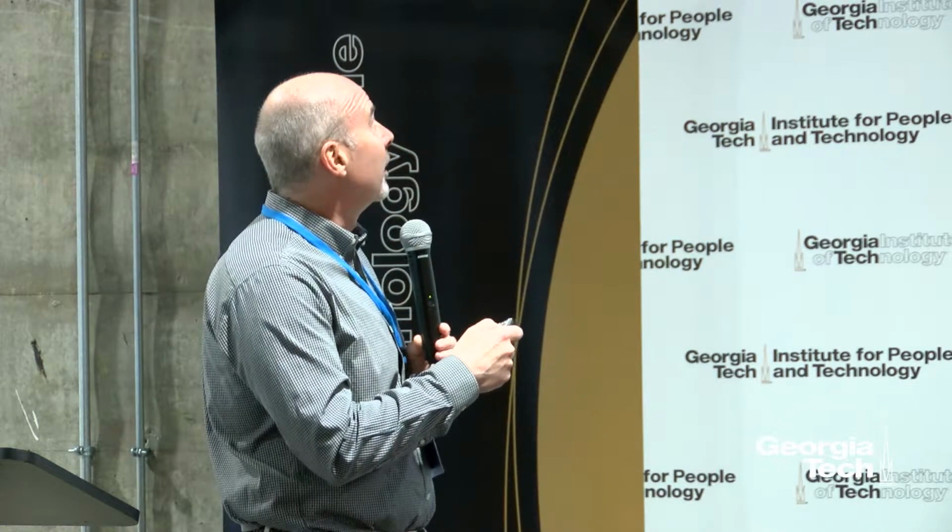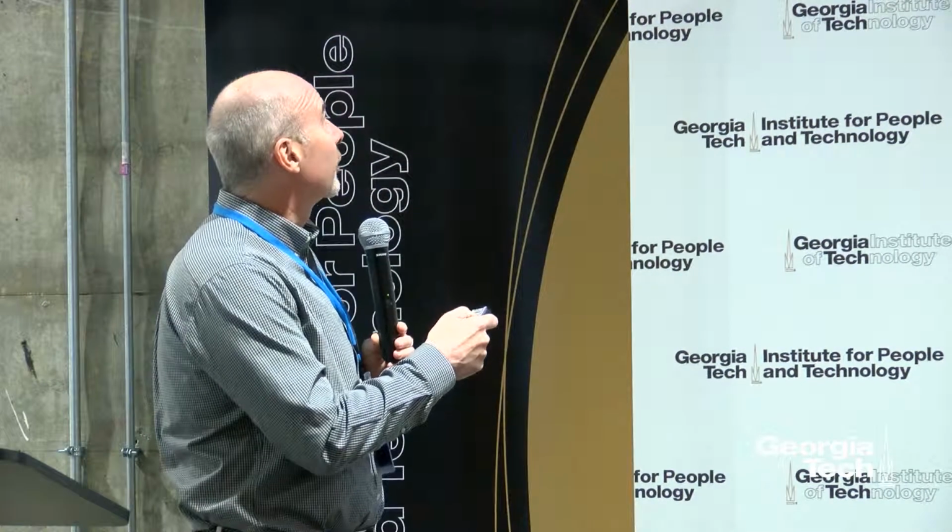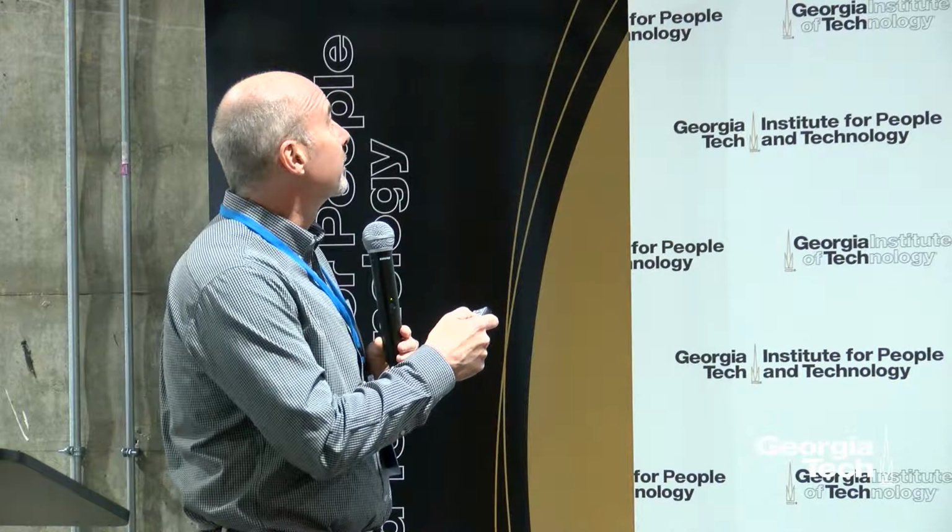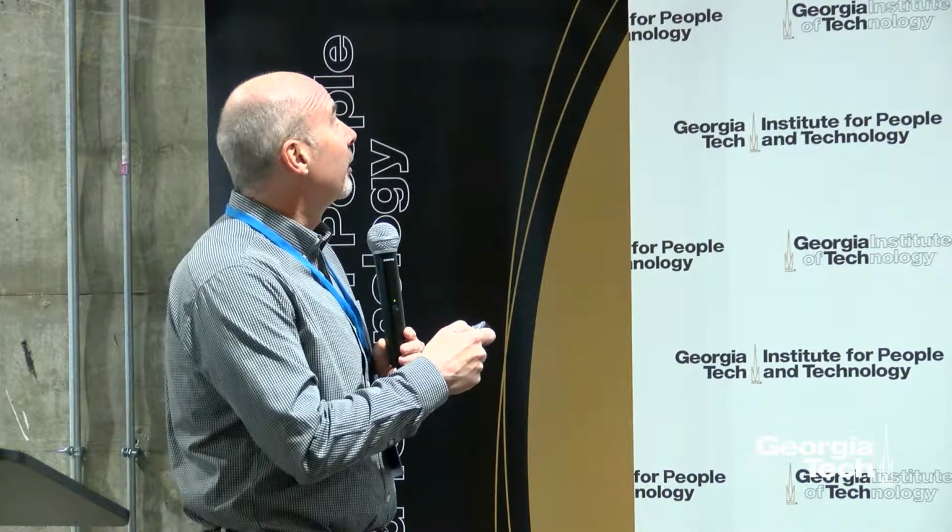And you can see this is actually our second case where we made 2 devices they implanted, and we could make changes in the device to allow the devices to be put at basically the carina, which is where the mainstem bronchi branch off. And we sat down with the surgeons on a Wednesday, we designed this on a Thursday, and we built it on a Friday. So you can make a complete de novo medical device in basically 3 days.